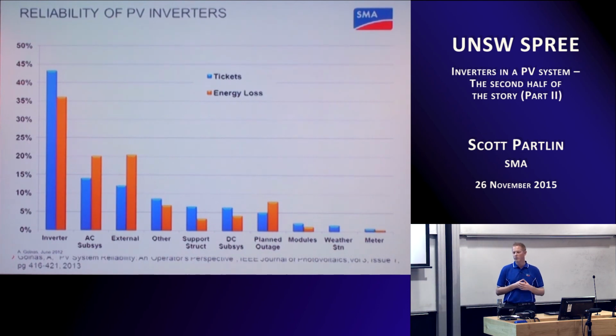And that, I'm pretty sure, is the same as what John from Solar Analytics was presenting. He talked about how the inverter can tend to be the least reliable or the most problematic part of the system. So, in their experience of their many gigawatts, over 40% of all the problems that they had reported across those plants were related to the inverter. So it gives you a sense of the scale. And in terms of the energy lost from all of their faults with plants all put together, more than 35% of that energy lost was a direct result of those failures.